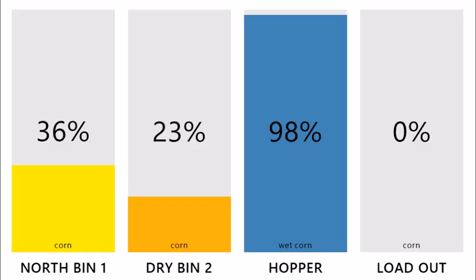Likewise, if our bin level hits 20%, we will trip the low alarm. Recall that our low reset level was set to 28%. That means that as long as our bin is less than 28% full, the system will continue to show an alarm. When we exceed our reset level, our alarm will reset.